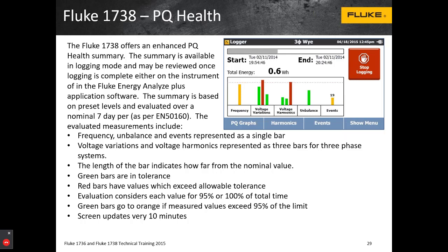The 1738 allows you to evaluate your measurement information that you've been recording and then compares it against a standard, which in this case would be EN 50160. Basically how it works is you can see in the color graph window here, it's showing you the frequency, the voltage variations, and the harmonics — these are all parameters.